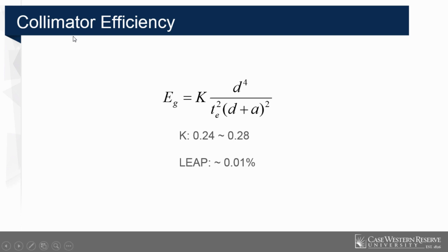For example, the collimator has its efficiency. LEAP here, low energy all-purpose parallel collimator. Look, only 1 out of 10,000 photons passes through. That's why nuclear medicine is sometimes called unclear medicine, because we're constantly starving for photons. And that's why we need iterative reconstruction. Otherwise, filtered back projection will be too noisy and full of image artifacts. You remember that.